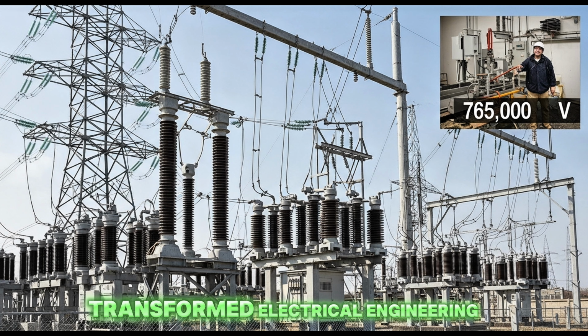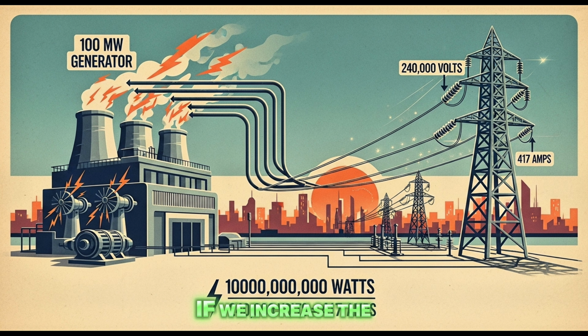Here's the insight that transformed electrical engineering. If we increase the voltage by a factor of 100, we decrease the current by the same factor of 100 to deliver the same power. But because power loss depends on current squared, reducing current by 100-fold reduces losses by 10,000-fold.